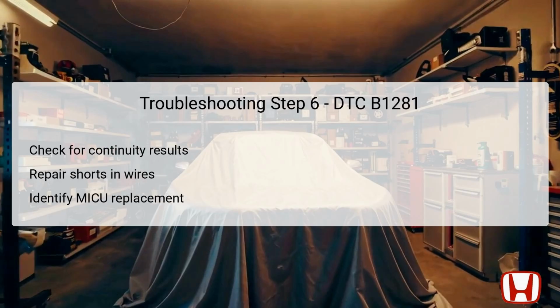In this sixth troubleshooting step, the focus is on the continuity results that have been gathered from the initial checks. If there is confirmed continuity between the specified wire terminals, this indicates that the wiring setup is appropriate and signals are likely traveling correctly through the circuits. This would lead to the conclusion that there may be a need to repair a short between the wires if a fault is identified. Conversely, if continuity is found to be absent, this suggests that the issue may lie within the MICU itself.